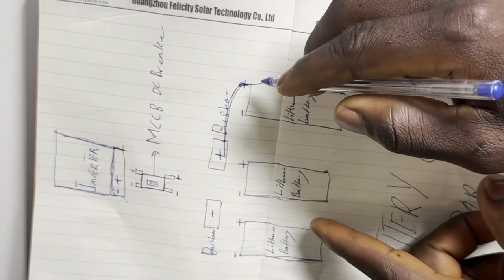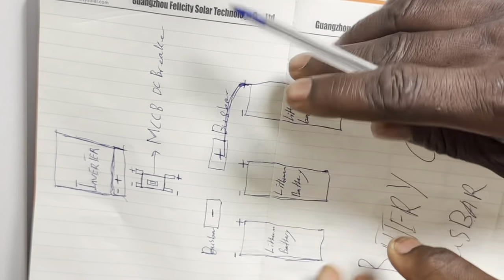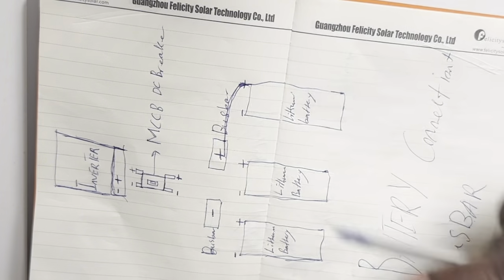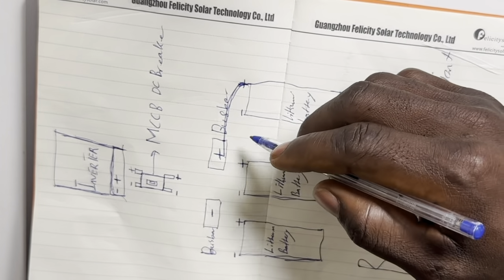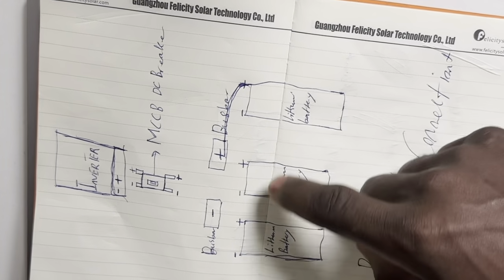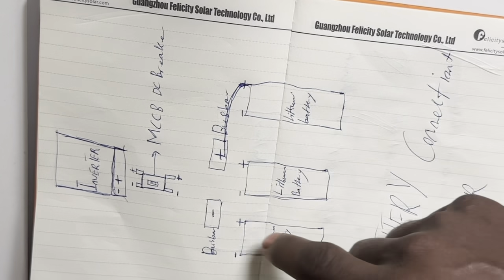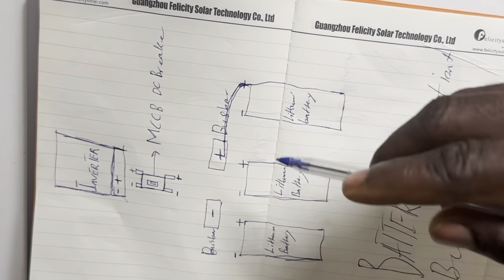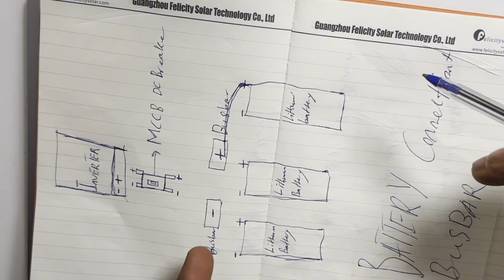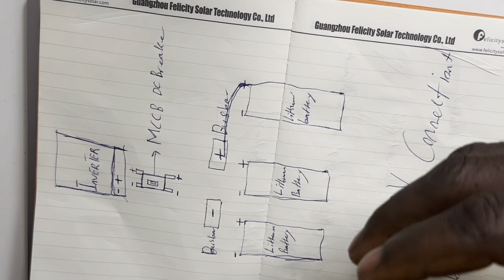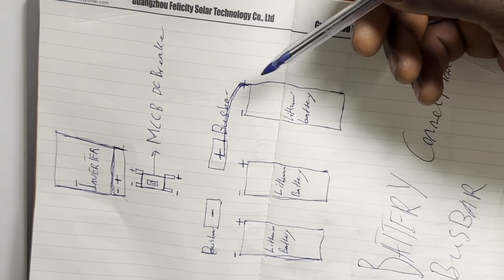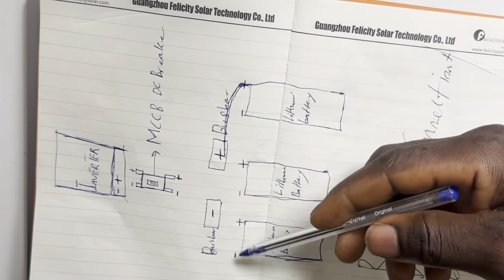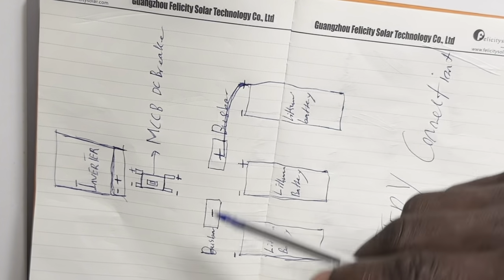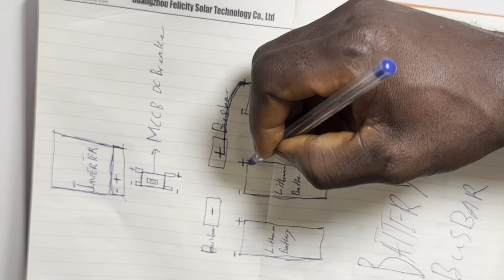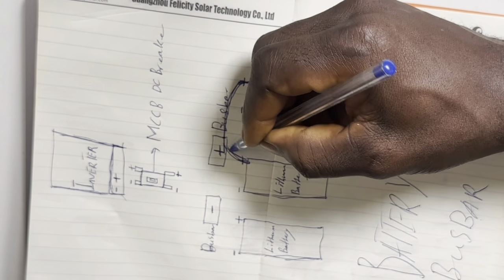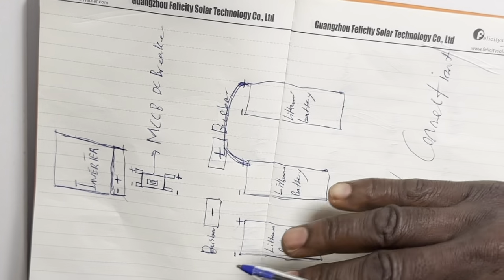Once you cut this cable, use it as the sample to measure the other cables, because one of the principles of using a bus bar is that all cables going to each bus bar must be the same length, to give the bus bar good, effective functionality. So you measure and cut each cable to match, even the one very close to the bus bar - make sure it has the same length as the others. That is your first step.